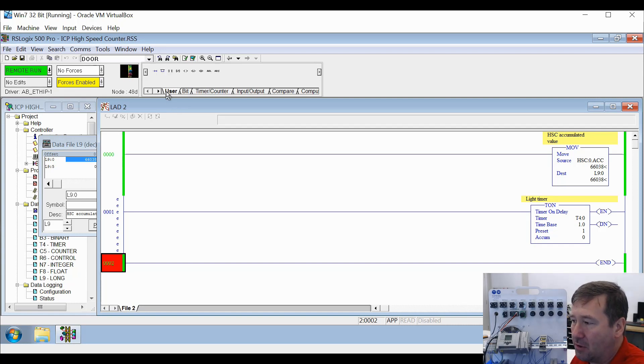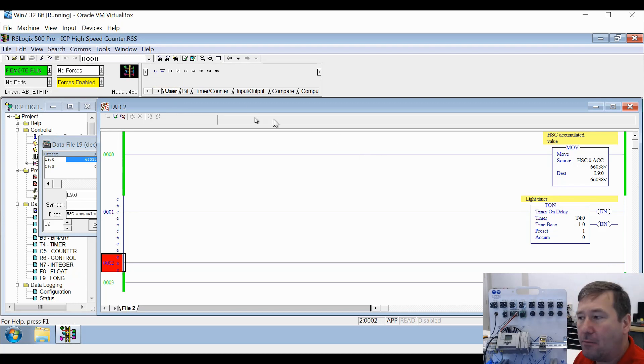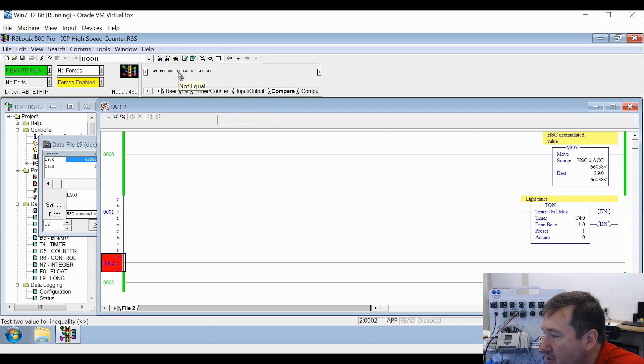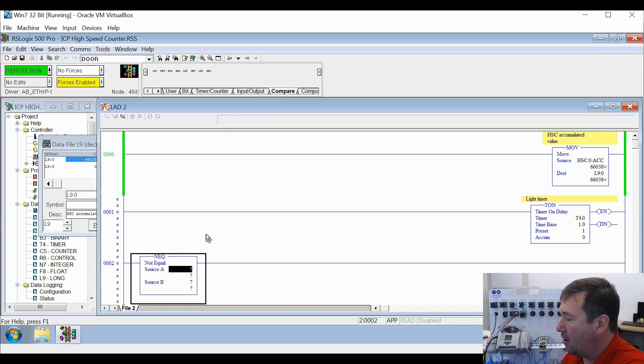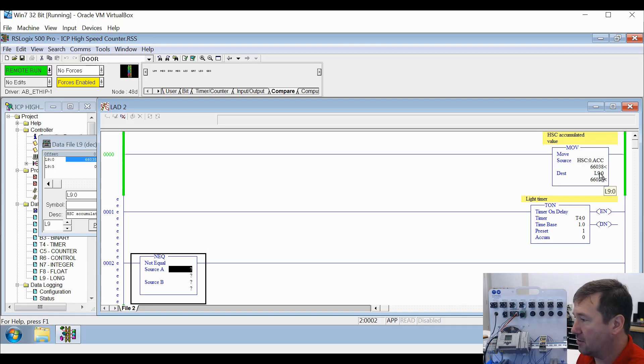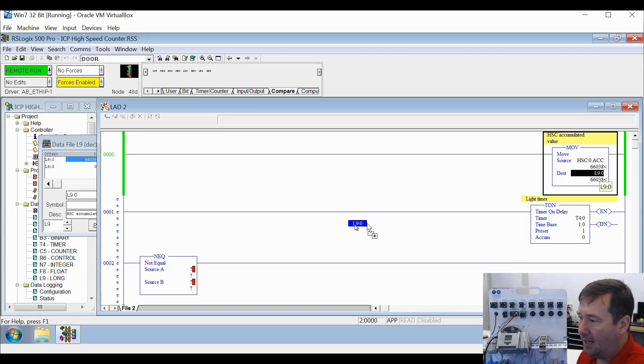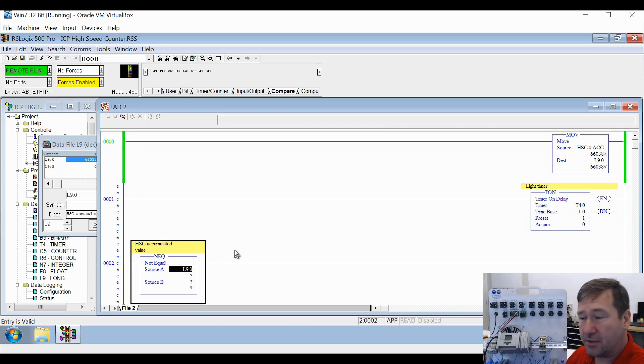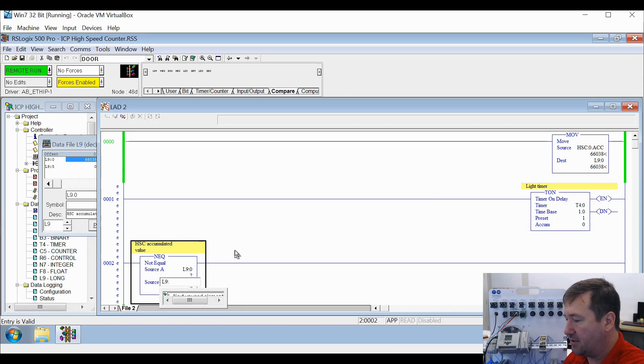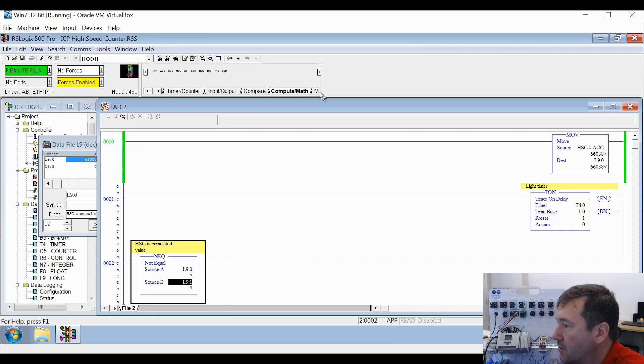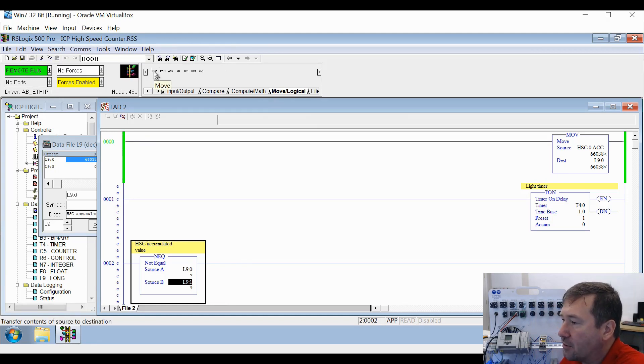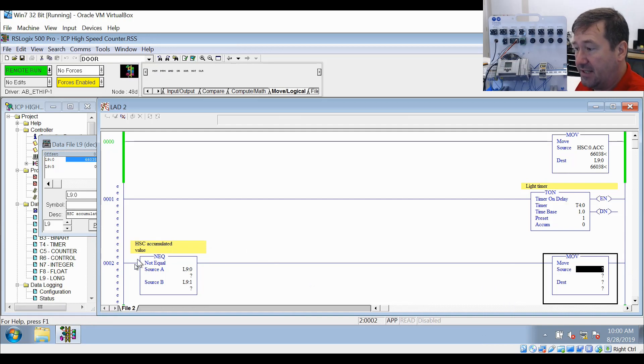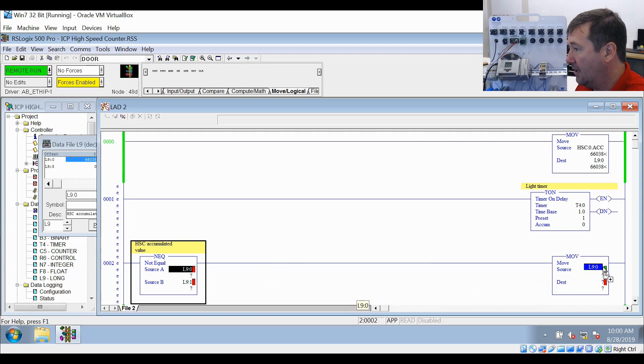Now we're going to add a second rung. We'll go to the compare tab and find the NEQ instruction - that's a not equal to instruction. For source A, we're going to use L9:0. I can click it and drag it until it's green - that's helpful for longer data addresses to make sure you get the right one. For source B, we're going to use L9:1, which right now is unused. Then we're going to use a move instruction - source L9:0 and destination L9:1.